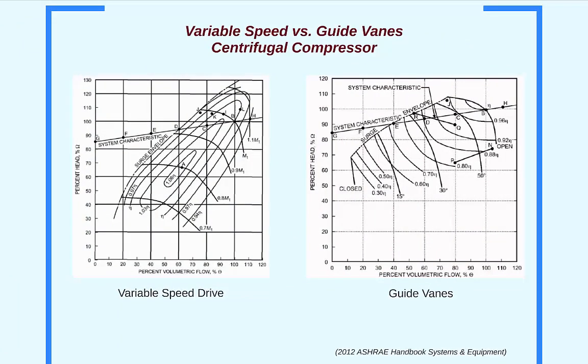Finally, compressors may be equipped with variable speed drives. The variable speed drives are more expensive, but also more efficient over the range of capacity. In many cases, the benefit of this control isn't worth the initial investment. Shown here are the performance of variable speed drives and inlet guide vanes. You can see at operating point D, the efficiency of inlet guide vanes is 88%, while the efficiency of a variable speed drive is 94%. In many cases, the cheaper inlet guide vanes will provide a better life cycle cost solution.